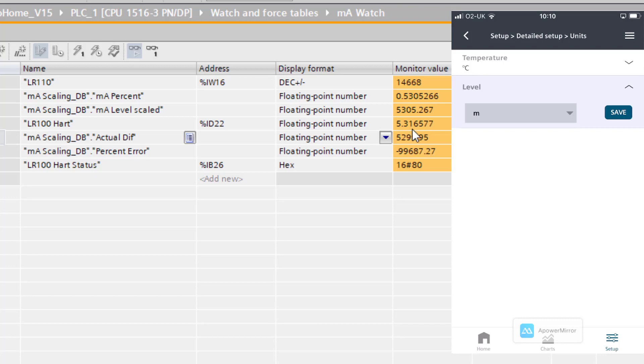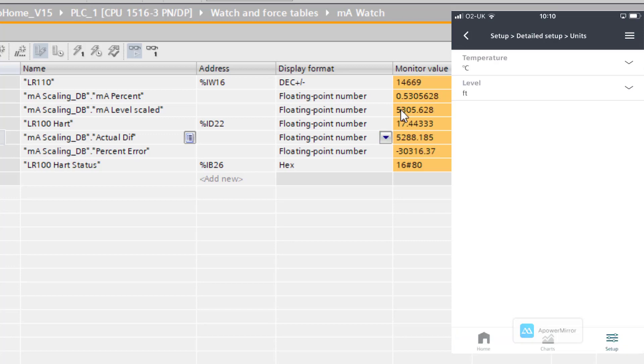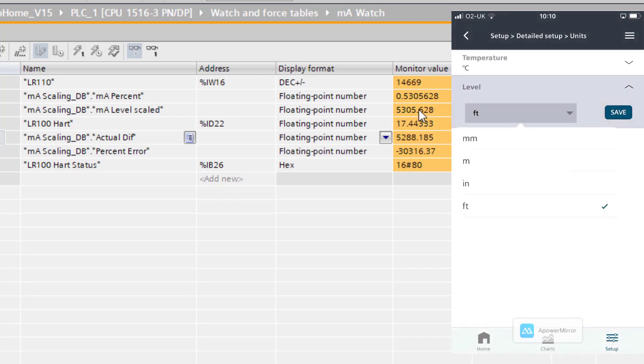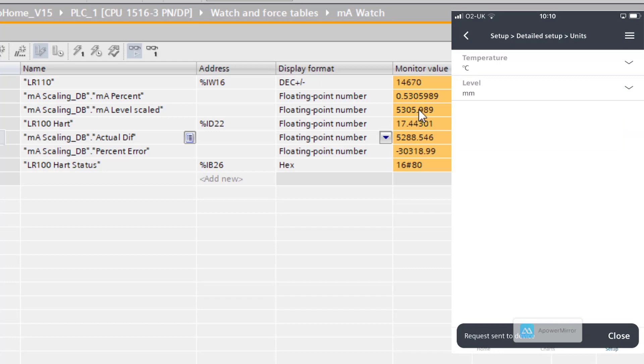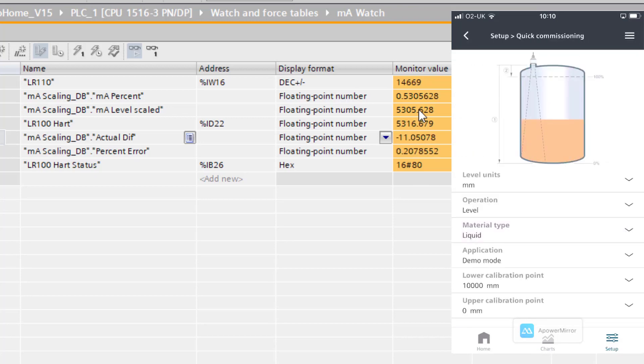That's not a massive issue, but if I was reading volume I could start to have problems. I'm just going to put this into feet, and straight away if I put it in feet I have got a problem. If I look at my device and my PLC, the units are completely wrong. So I'm going to put this back into millimetres and then do something a little bit more drastic that could cause a spill or could cause you to run out of product.